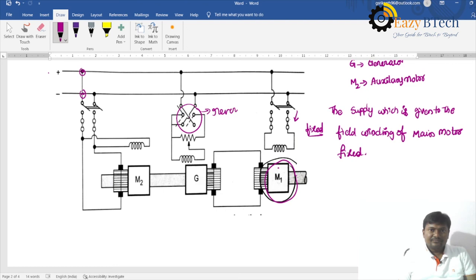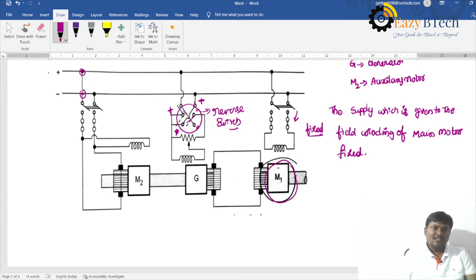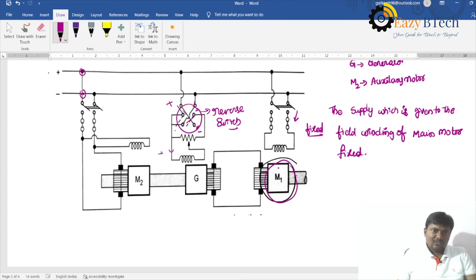A reversal switch is provided for the generator field. When connected in one position, plus is connected to one terminal and minus to the other. If connected in reverse fashion, the polarity reverses — the top terminal becomes minus and the bottom becomes plus — allowing the direction of the motor to be changed by moving the switch.